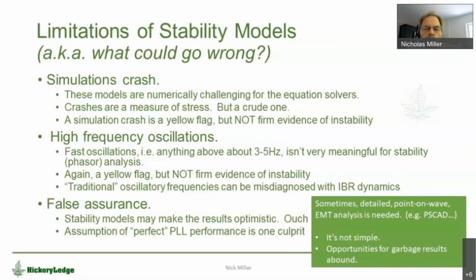So anything that's moving faster than 3-5 hertz isn't very meaningful for phasor analysis, and people will debate what that upper limit is, but really fast things can't be captured. So if you start seeing your simulations oscillating at 10 or 20 hertz, it says something's wrong, but it doesn't really tell you anything else beyond that.